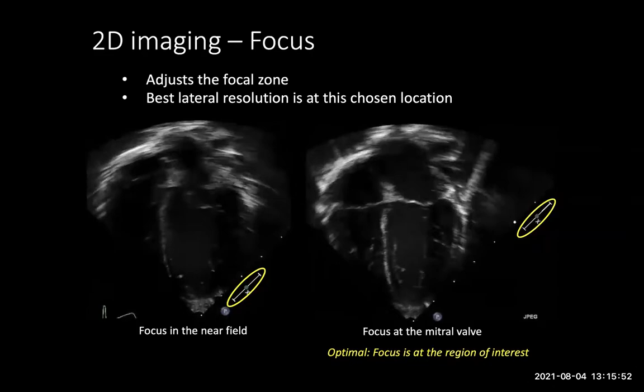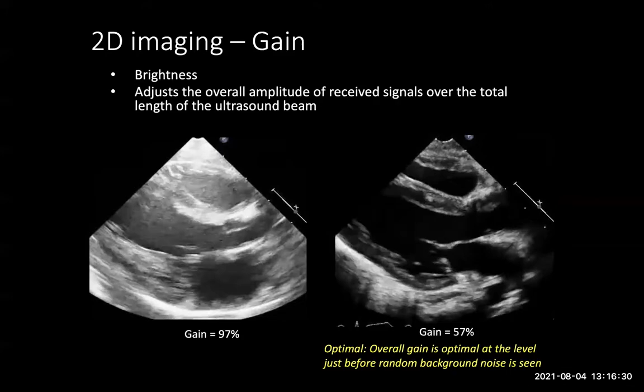The gain setting is the brightness of the whole image. It adjusts the amplitude of all signals that are received. The image on the left has a gain setting of about 97%, which is much too high, where the heart is not only too bright, but there's also a lot of background noise in the blood pool. To find the right amount, we can decrease the overall gain until you see a minimal amount of speckling in the blood pool, and then decrease it just one more step so that the speckling is gone. And here we have a gain of 57%. So the overall gain is optimal at the level just before random background noise is seen.